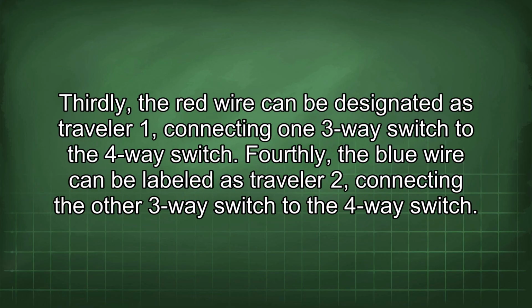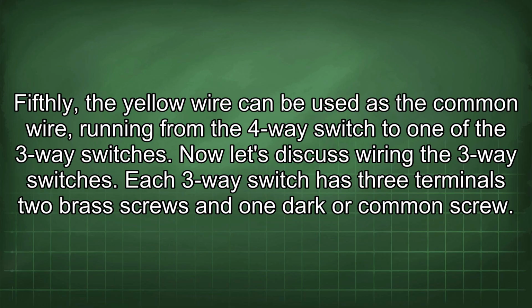Thirdly, the red wire can be designated as Traveler 1, connecting 1 3-way switch to the 4-way switch. Fourthly, the blue wire can be labeled as Traveler 2, connecting the other 3-way switch to the 4-way switch. Fifthly, the yellow wire can be used as the common wire, running from the 4-way switch to one of the 3-way switches. Now let's discuss wiring the 3-way switches.